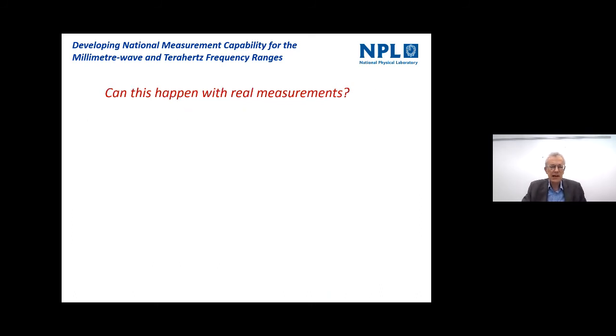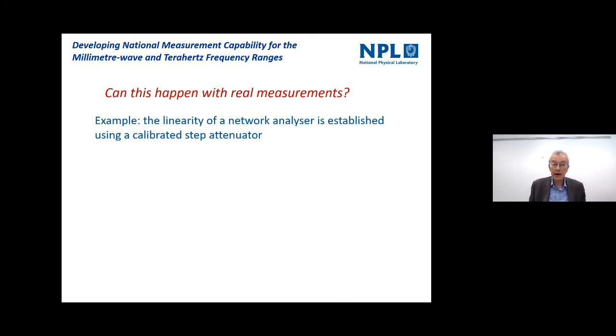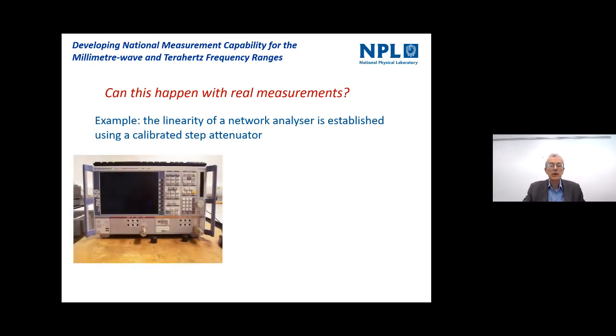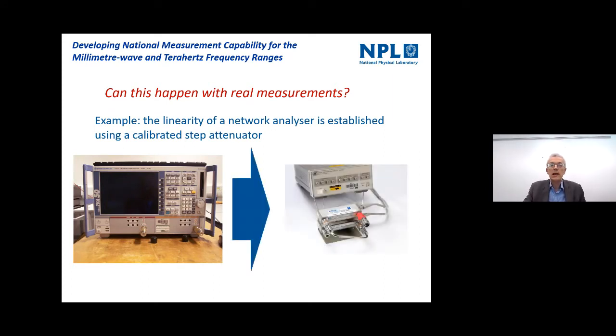You might say, well, can this happen with real measurements? So I'm going to show you an example now of where it can happen in laboratories, in real laboratories. And this relates to providing traceability for network analyzers, vector network analyzers. And typically one way you can do this is by using a calibrated step attenuator. So you take your network analyzer, shown here on the left, and you calibrate it, if you like, with respect to a calibrated step attenuator, which gives you known values of attenuation.